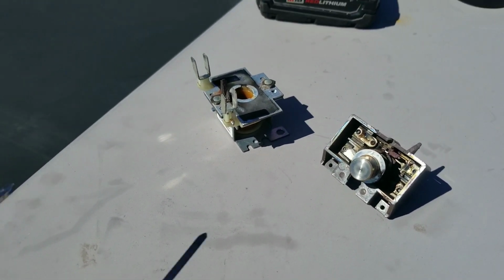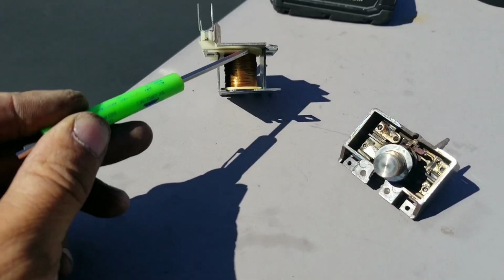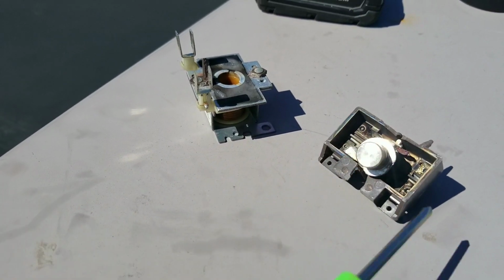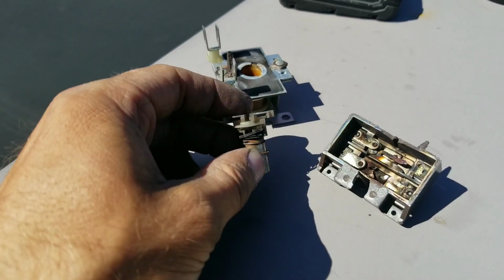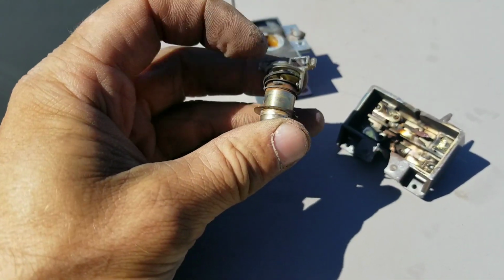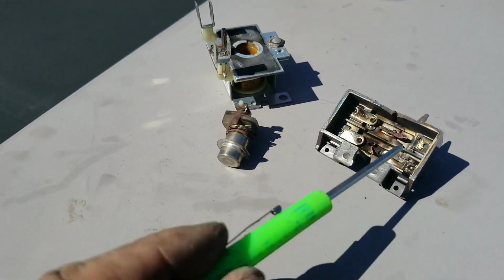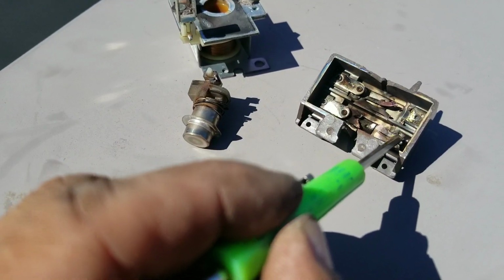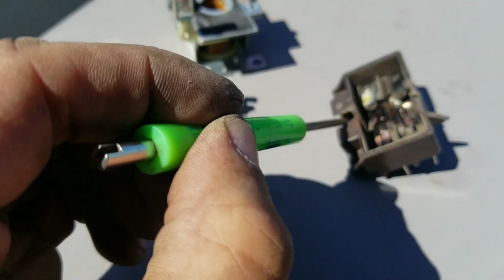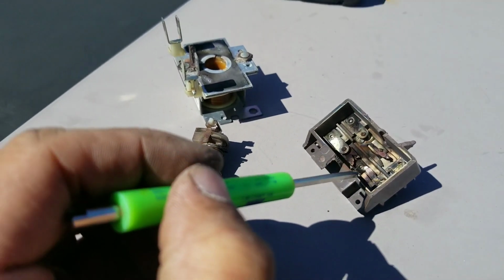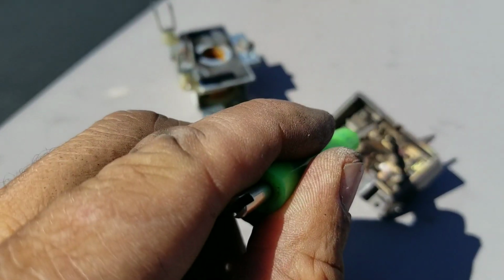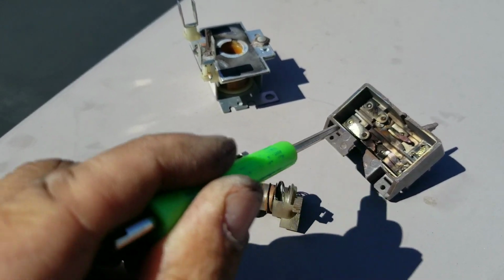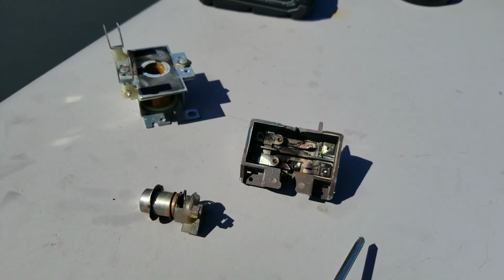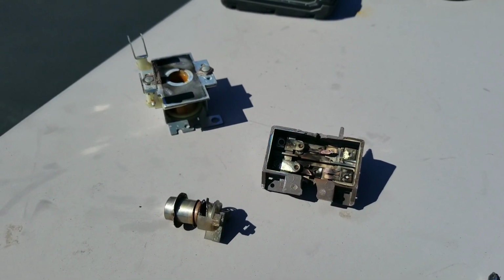Just for the heck of it, I decided to pull this switching relay apart. So here's the base of our relay with our solenoid coil on there. And this is the inside of our relay. Let's see if we can pull this little solenoid right out of there. So there's our little plunger that goes inside there, and you can tell that spring is pretty burned up and melted. But if you look inside there, all of our terminal contacts are melted and destroyed. So my idea of why our breaker tripped is obviously this shorted out internally, and through this plunger, through this spring, which is partially melted, it probably connected one line to the other line, and that's what tripped our breaker. So that's our culprit, guys. That's the gratification we're looking for today.